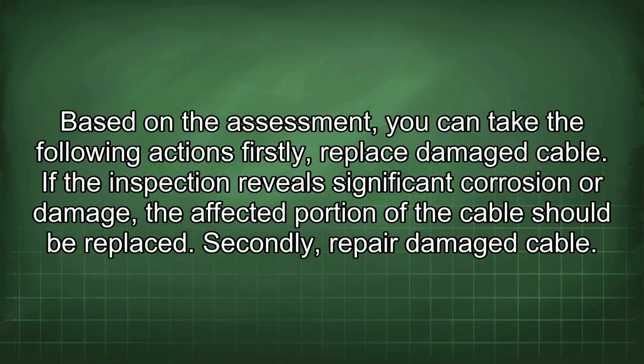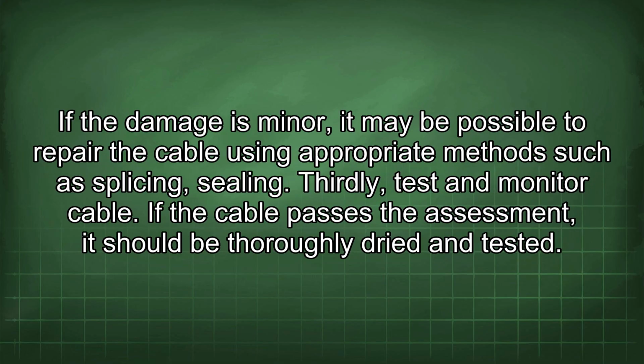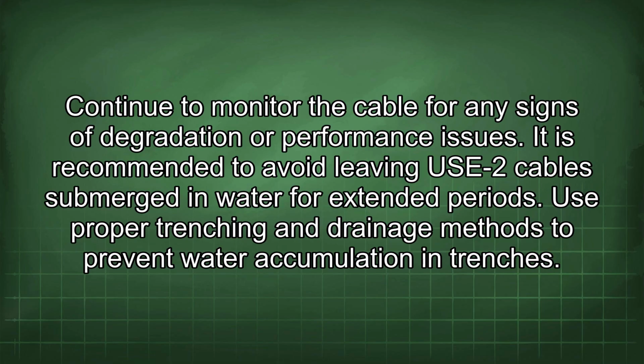Based on the assessment, you can take the following actions. Firstly, replace damaged cable. If the inspection reveals significant corrosion or damage, the affected portion of the cable should be replaced. Secondly, repair damaged cable. If the damage is minor, it may be possible to repair the cable using appropriate methods such as splicing, sealing. Thirdly, test and monitor cable. If the cable passes the assessment, it should be thoroughly dried and tested. Continue to monitor the cable for any signs of degradation or performance issues.